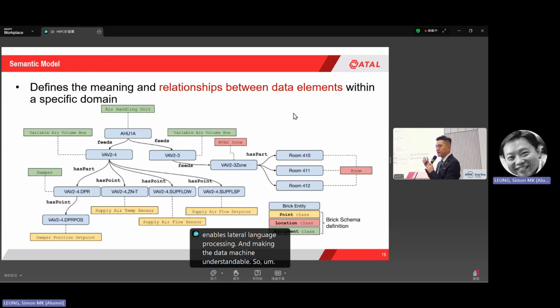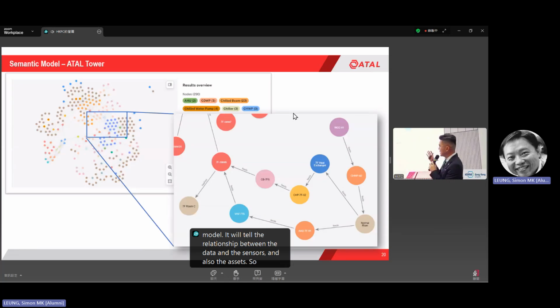So when we have the semantic model, it will tell the relationship between the data, the sensors, and also the assets. So this is the tower. We build a semantic model, and we can see that in zone 6, we have these VAV boxes. This VAV box will serve the cooling to this zone, and this VAV is connected to this AHU. So we can know the whole relationship.